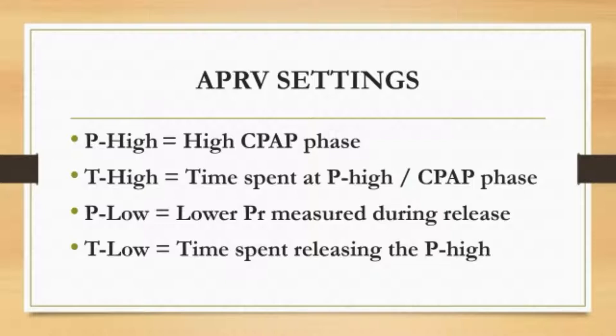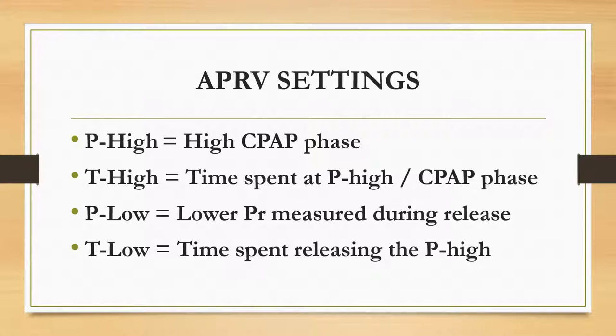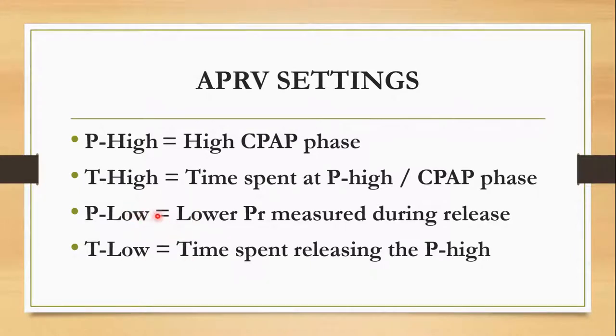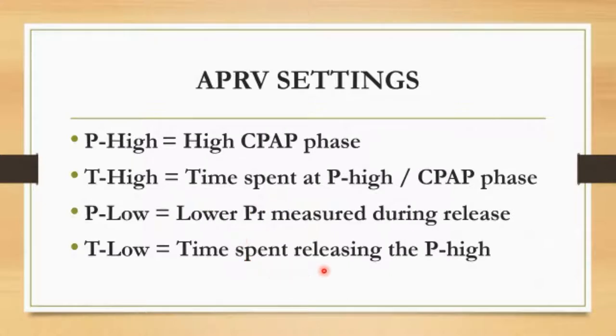When looking at APRV settings, there are four unique settings: P-high, T-high, P-low, and T-low. The P-high is a high CPAP phase, and T-high is the time spent at that P-high/CPAP phase. The pressure low is the lower pressure measured during the release, and T-low is the time spent releasing the P-high. Importantly, P-low is measured, not set — which makes time-controlled adaptive ventilation very unique.